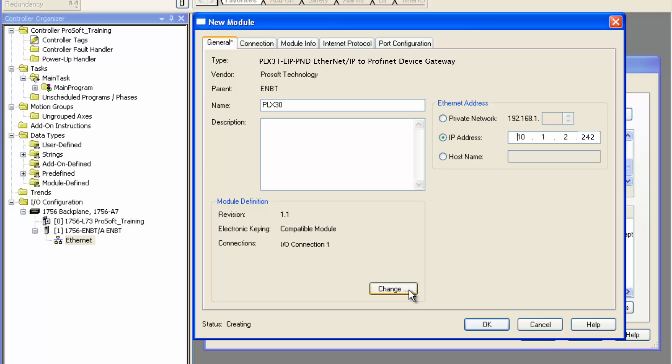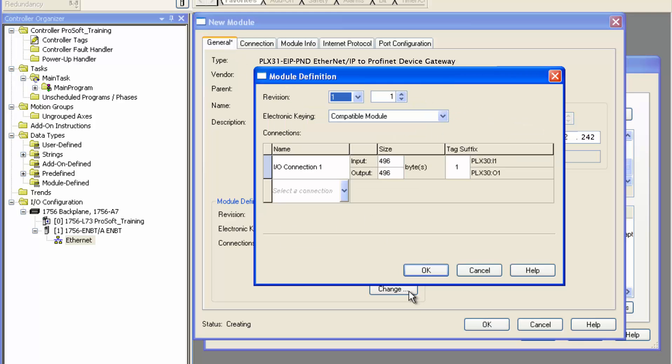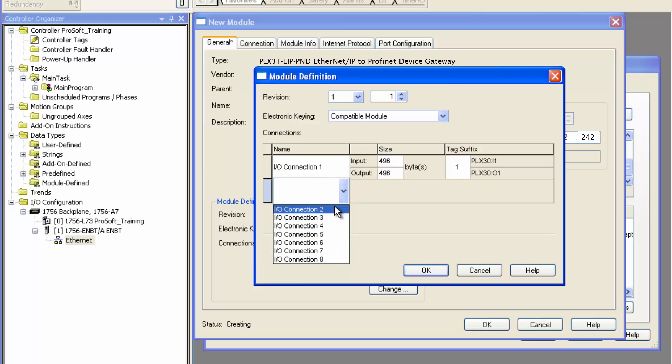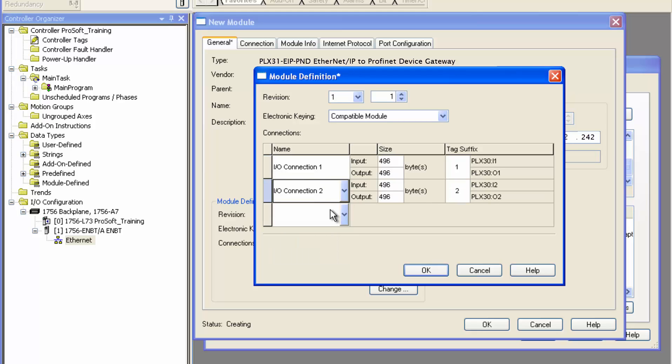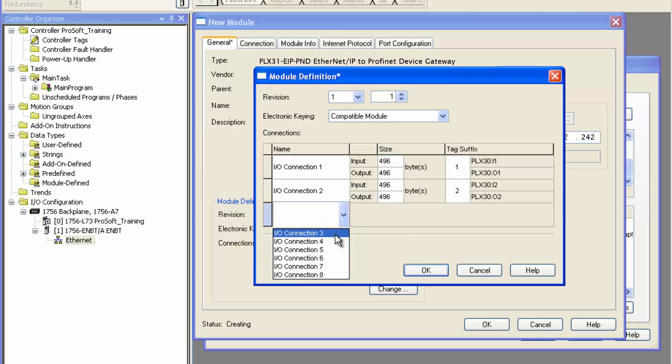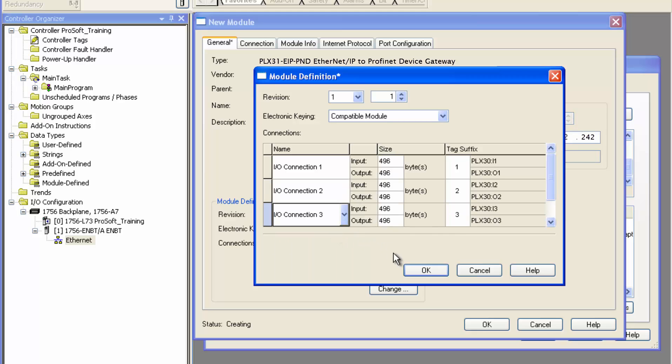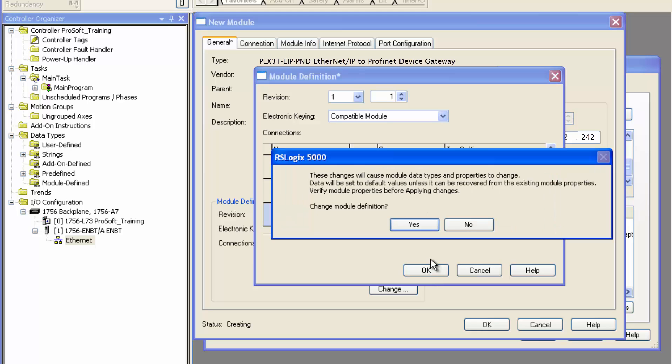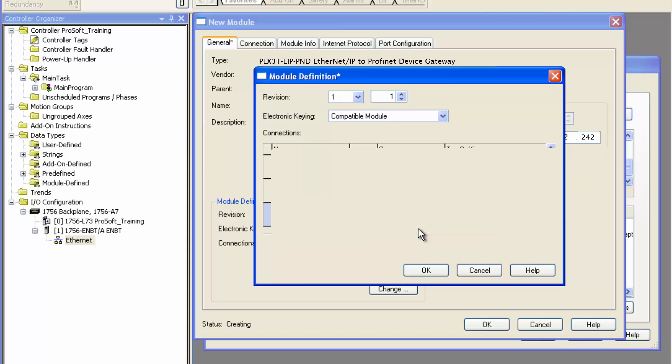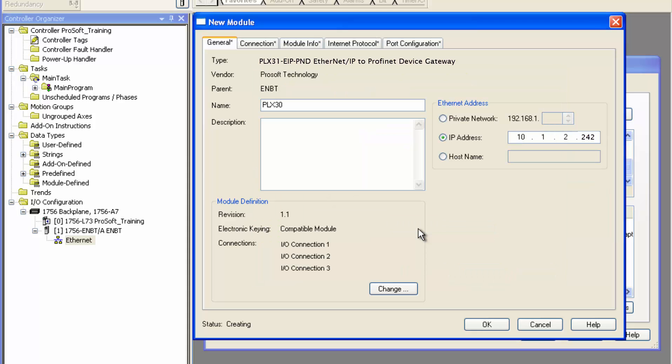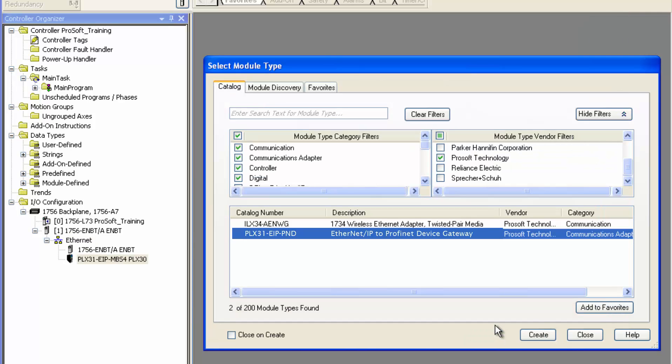Back on the general tab is where you add multiple connections to the gateway for your Rockwell processor by clicking on the change button under module definition. From the drop down window under connection one, select additional connections. I'll set up three connections here. It's possible to add up to eight connections. Once you're finished, click OK and click close to exit the window.